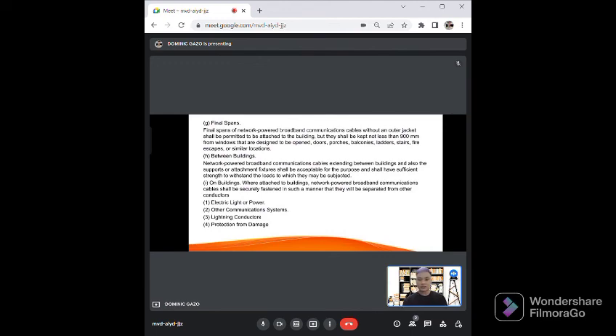For between buildings, network powered broadband communications cables extending between buildings, these supports or attachment fixtures shall be acceptable, and of sufficient strength to withstand the loads to which they may be subjected. And we have on the buildings, where attached to buildings, network powered broadband communications cables shall be securely fastened in such a manner that they will be separated from other conductors. We have electric light or power. This network powered broadband cable shall be separated by 100 millimeters from electric light and power.